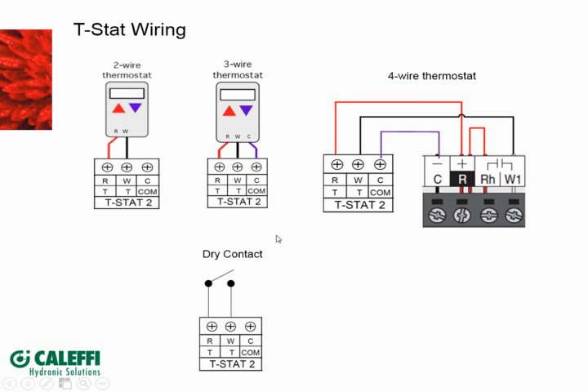And then the last thing is just a dry contact, which is obviously similar to a 2-wire stat, or it could be like a mercury bulb type of stat. But even if you had whatever your configuration is, if you were pulling off of an end switch from a zone valve or some other control, you just need a dry contact here, and that'll pop it and initiate that heat demand. And another common one there is guys that are doing snow melt, they want to put like a 12-hour spring-wound timer on to run the snow melt instead of some kind of automatic control. That's where you'd hook it up.